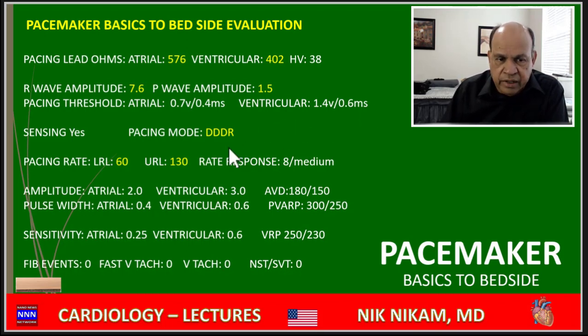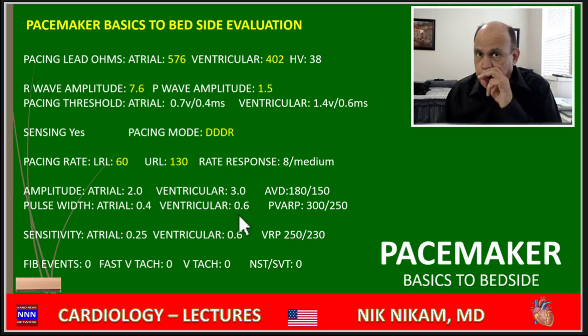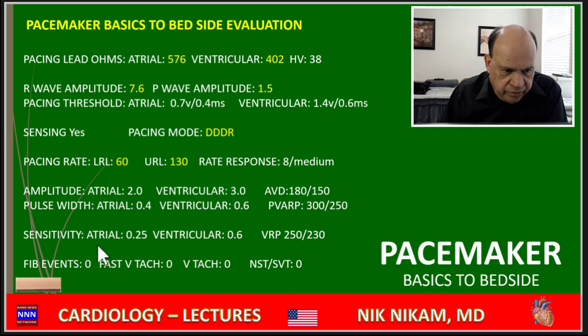So that tells, and this DDDR, that's the functionality of the pacemaker. Dual chamber sensing, pacing, inhibitor or triggered, and rate responsive. This is a lower limit of the rate, upper limit of the rate. And then we have this energy that is used, the atrial amplitude is 2 volts for 0.4 milliseconds, 3 volts for 0.6 milliseconds. So the sensitivity of atria is 0.25, ventricle is 0.6. That means it can pace its ventricles and atria without much effort.